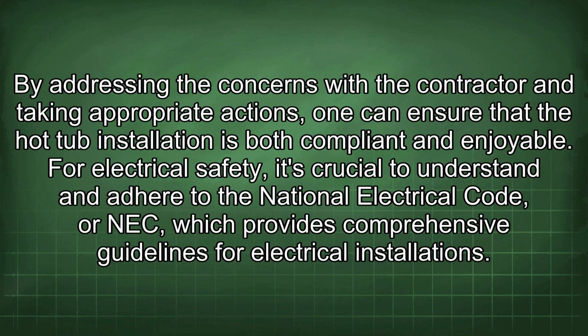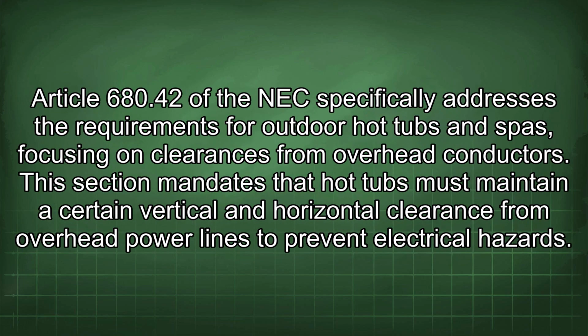For electrical safety, it's crucial to understand and adhere to the National Electrical Code, or NEC, which provides comprehensive guidelines for electrical installations. Article 680.42 of the NEC specifically addresses the requirements for outdoor hot tubs and spas, focusing on clearances from overhead conductors.